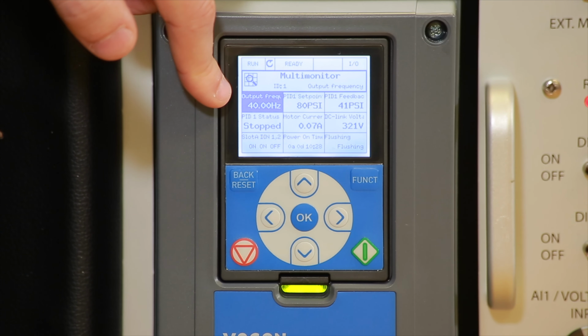US is fine for daylight savings time. Because we have a battery-backed real-time clock inside the drive, we can program the date and time inside the drive. So if anything should happen or we want to program when the drive runs, we can actually use this. So there is a battery inside this VACON 100 flow, and it's fantastic because of the real-time clock. So many benefits come with this, and you will see soon why. So we're going to leave the time and date the way it is, year 2018. The date you could change as you see fit.